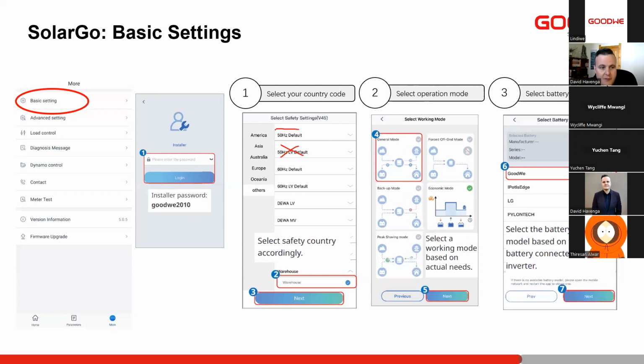If we need a wide range input, we can use 50 Hertz grid default. That doesn't comply to any national standards; it's just a wide operating range. So if the grid voltage is quite unstable, we can use that. But if we want our inverter to protect everything on the output and make sure that the voltage is correct, then we will select a grid code such as South Africa, or whatever grid code or grid compliance your country complies to.